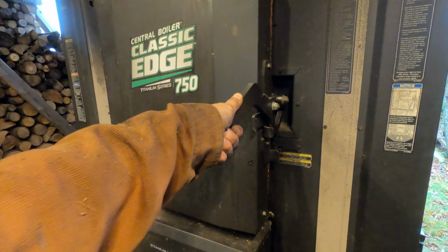So now what happens is when there's a zone calling, right now they're none calling, no heat, no hot water. When the return comes in from whatever is being called, say first floor baseboard, it'll go through that heat exchanger, get heated up, and come out here and then into the boiler. So it sort of acts as if the water in the boiler is hot enough, and then just goes to the zones, if that makes any sense.